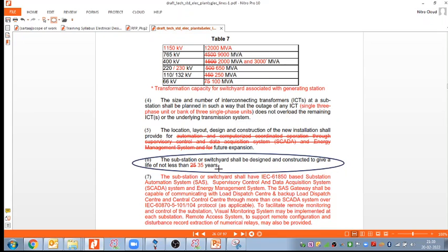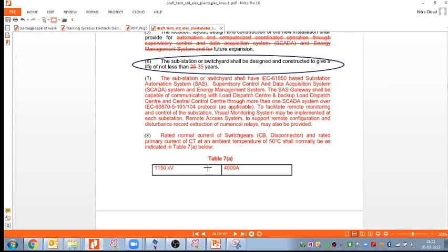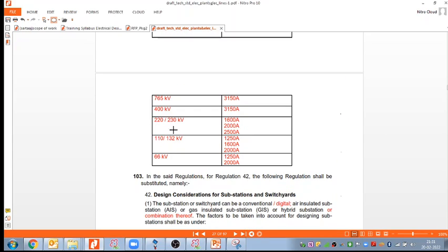So as a contractor, we are not aware about all the grid right now, how many total generators, how many total loads, we are not aware. The EPC contractor is not aware; that is controlled by the transmission planning department of the grid. So they are aware about their grid, the grid company. They will plan for the next 35 years, and based on that they will provide the current rating that should be selected, considering the future growth also.